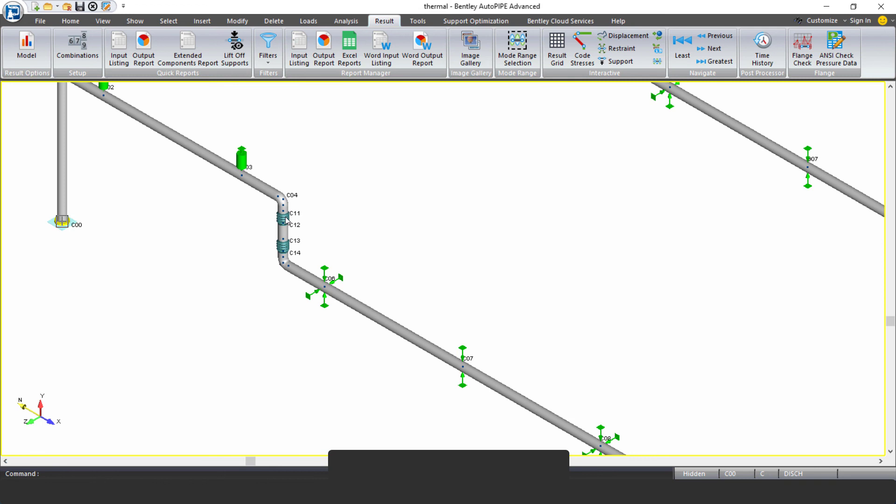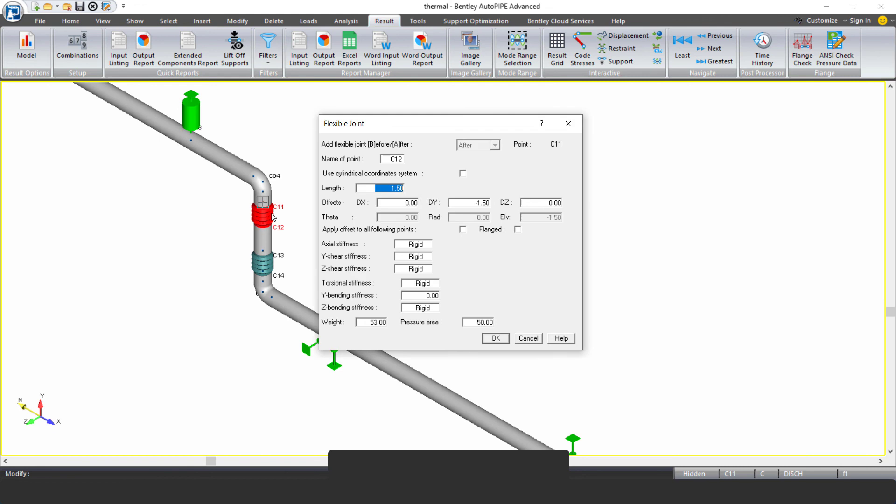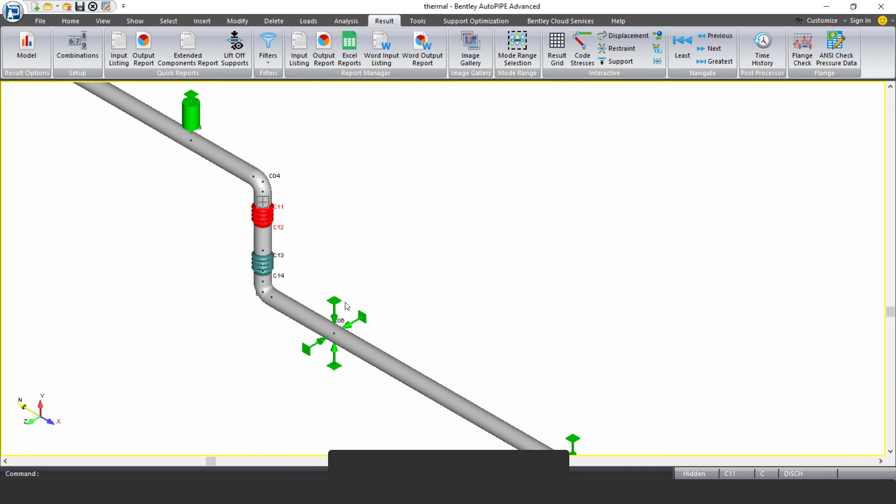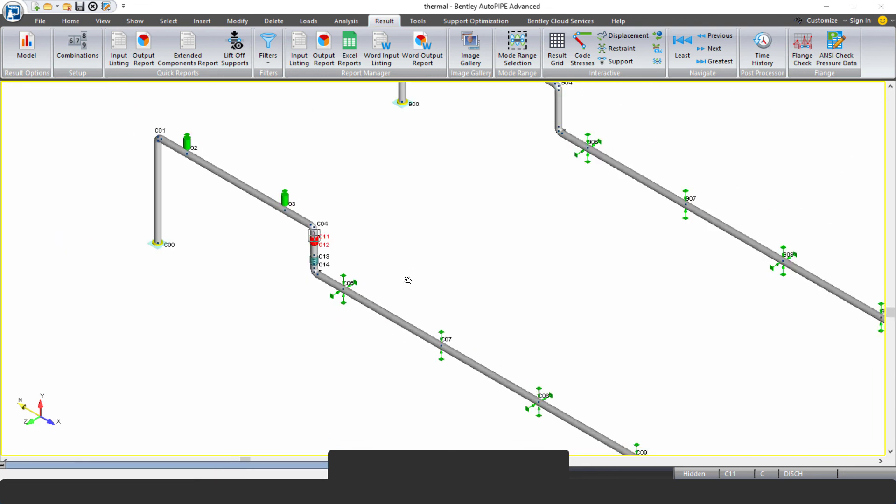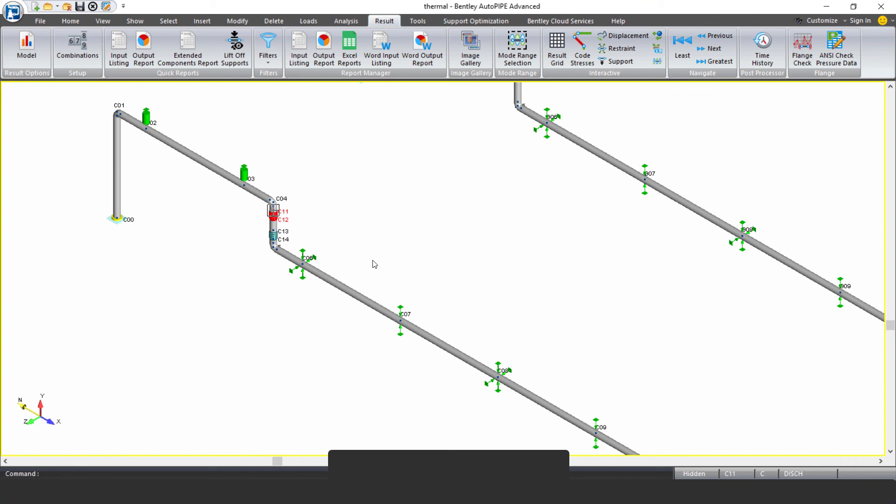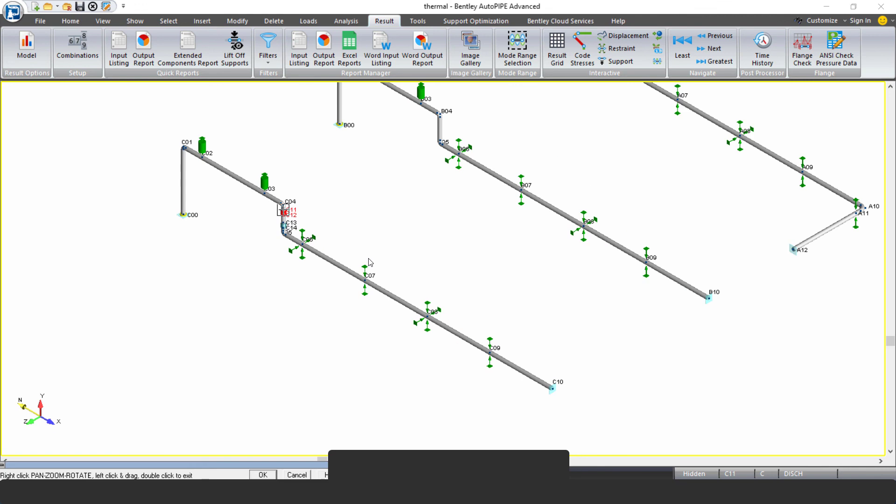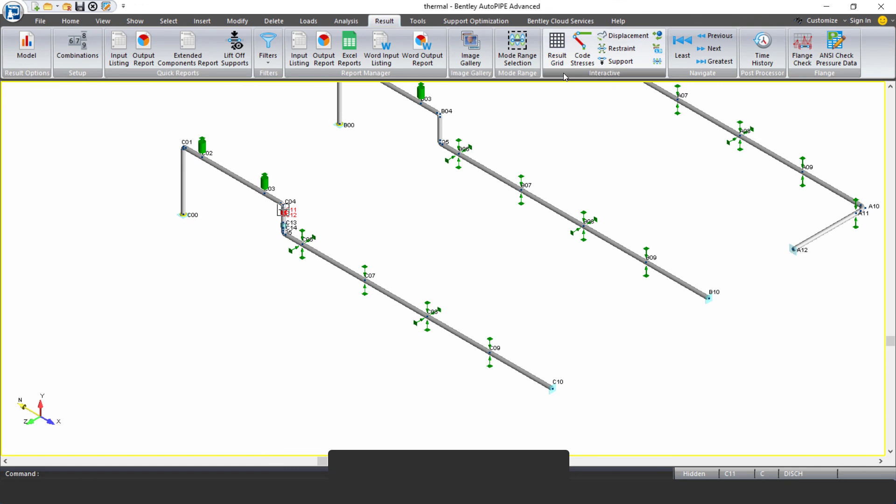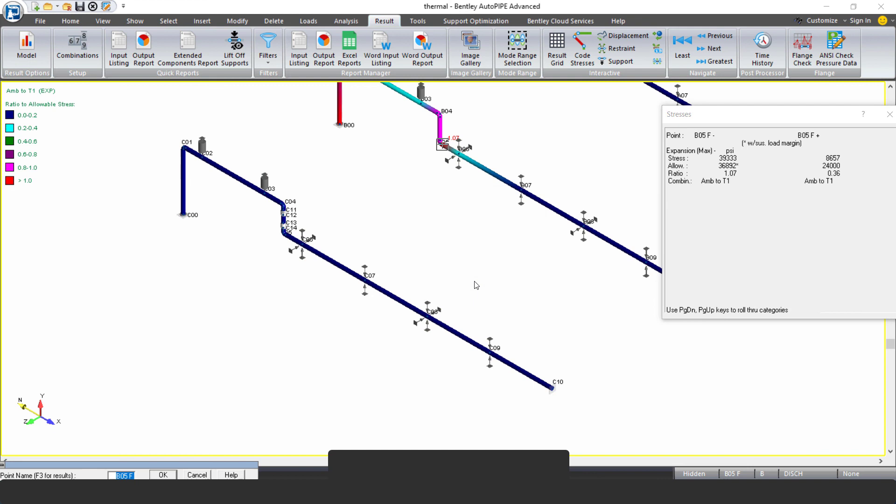We'll talk more about the specific types of expansion joints in just a moment. But these expansion joints, what we've allowed is just a Y bending stiffness released. So it's just taking bending in one plane in this vertical section of pipe. And hopefully this allows for the flexibility that we need so that we can accommodate the thermal growth. So again, if we analyze this and we look at code stresses thermal, we see that we were able to dissipate the thermal stresses in this pipe by like a ton, right? We have really, really low stress values now thermally throughout this piping.